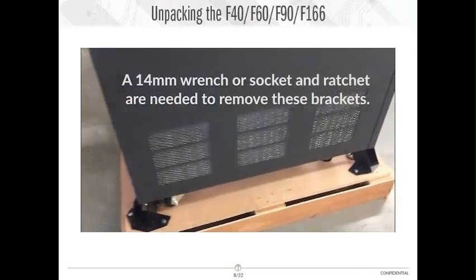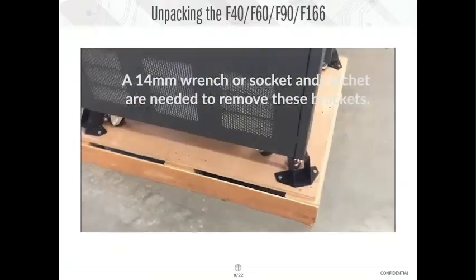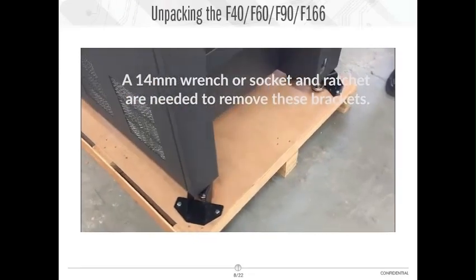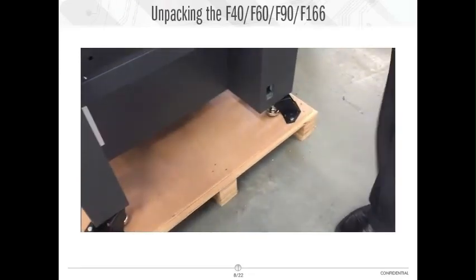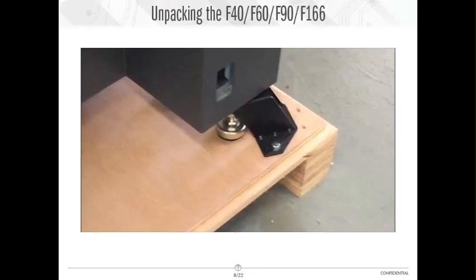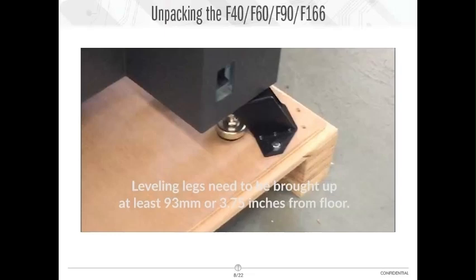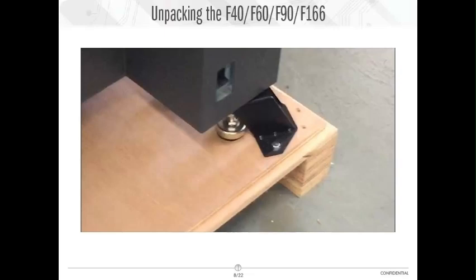To detach the brackets holding the legs, you will need a 14 mm wrench or socket, and a ratchet. Once the brackets are removed, the leveling legs will need to be brought up to at least 93 mm or approximately 3.75 inches from the floor to avoid damaging the legs when removing the printer from the pallet. With the F40 and the F60, the printer will need to be lifted from the pallet. Using a 2x4 you can create a step to roll the casters of the printer onto.